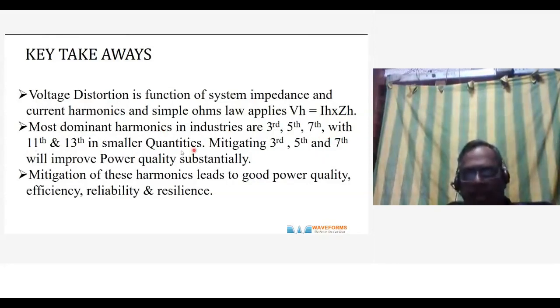Mitigating third, fifth, and seventh harmonics will improve power quality substantially. So this is the fact. If there are many industries that have done a power quality study, most of the major harmonics are third, fifth, and seventh. Once you tackle these three harmonics, you will solve the problem of voltage distortion and current distortion. And mitigating these harmonics leads to good power quality, efficiency, reliability, resilience. Not only that, your operating costs and your capital costs can all come down when you bring down your harmonics level.